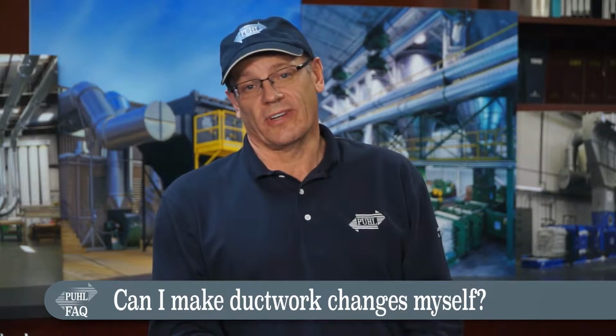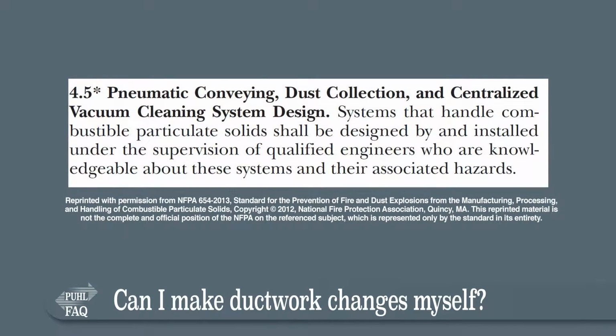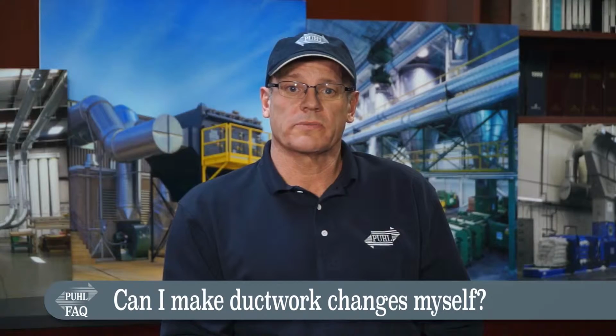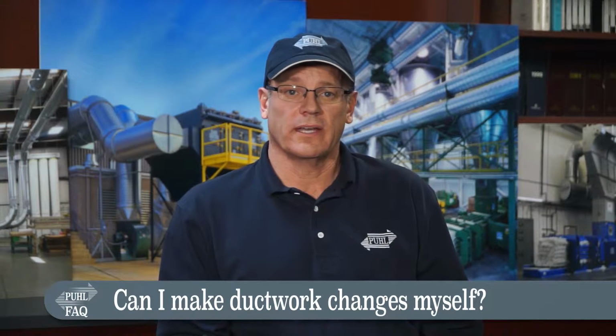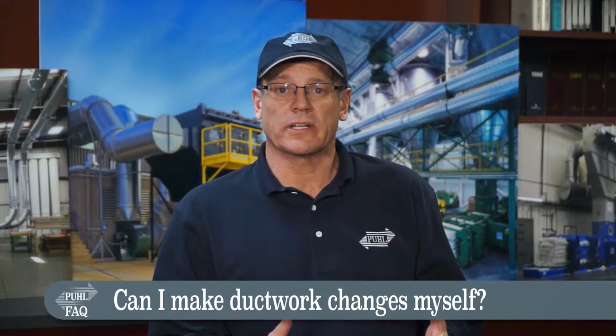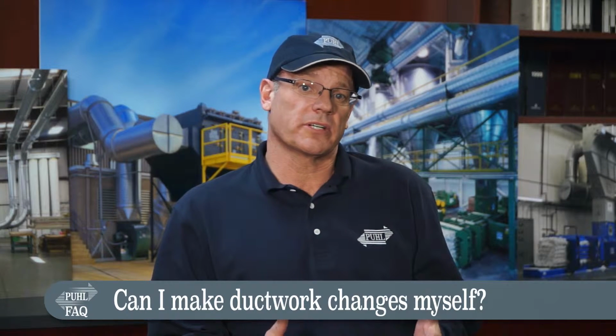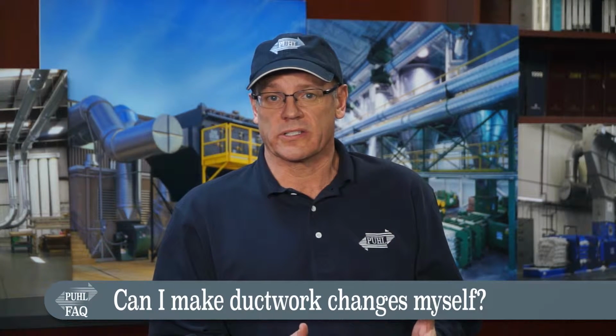Well, it depends on who you ask. The National Fire Protection Association advises against do-it-yourself ductwork projects. NFPA 654.4.5 states that systems conveying combustible particulate solids shall be designed by and installed under the supervision of qualified engineers who are knowledgeable about these systems and their associated hazards. Since a trim system conveys combustible dust, any changes to the ductwork have to be engineered so that the combustible dust and material don't accumulate in any one section of the duct.